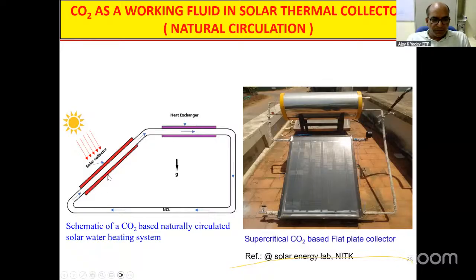The advantage here is: if you connect the water directly without a loop, in the morning during winter when it's getting heated, it will not start moving due to low temperature causing higher viscosity, so you won't get hot water. With CO2, even a small amount of heat gained will make it start moving toward the heat exchanger, delivering heat to the water there, and then it moves back.